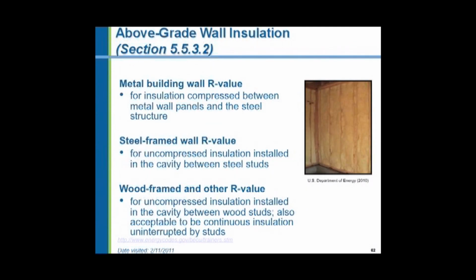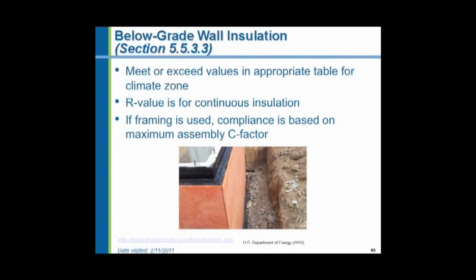Now, there's a metal building wall R value, a steel framed wall R value, and a wood framed and other type of wall R value. Each has its own details of how you're to install the insulation. Below grade wall insulation, we didn't used to have any for commercial buildings. Now we're required to have at least 1.5 inches of insulation. It's continuous insulation.